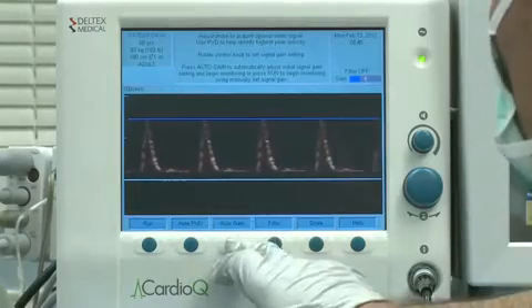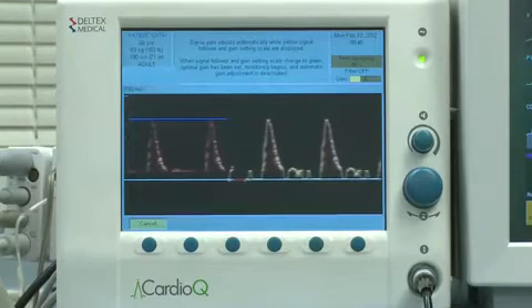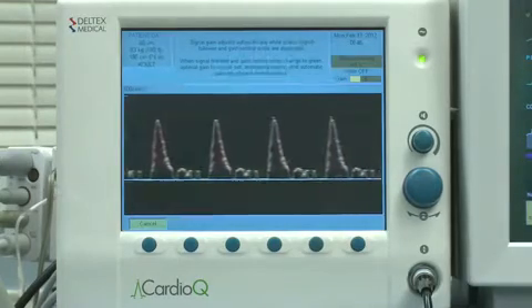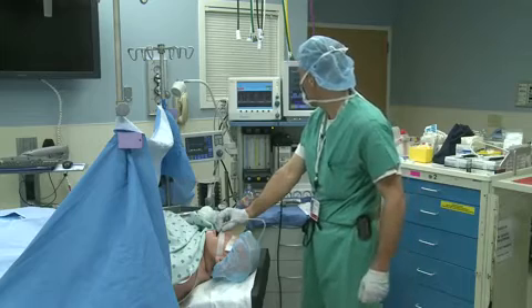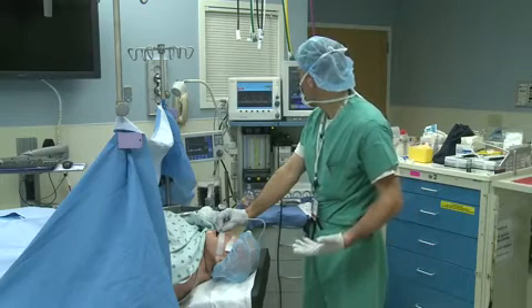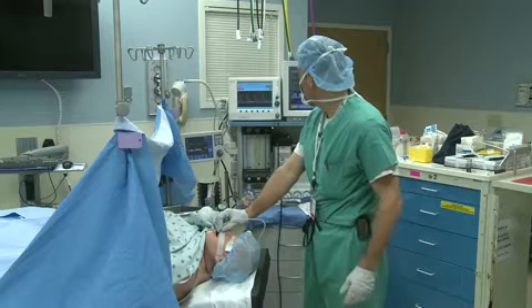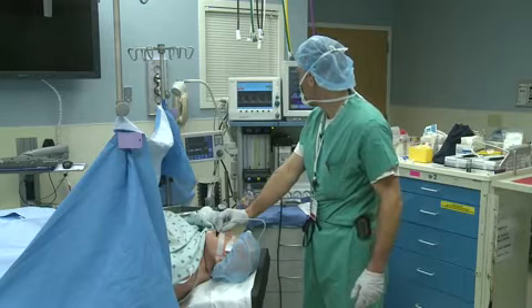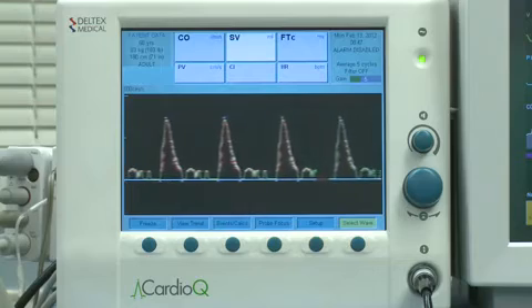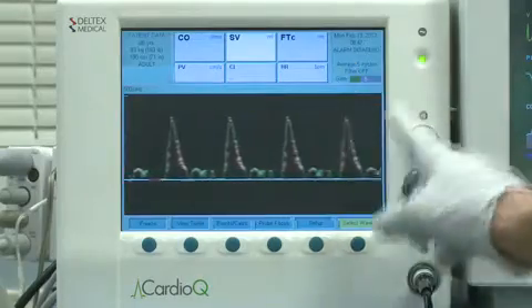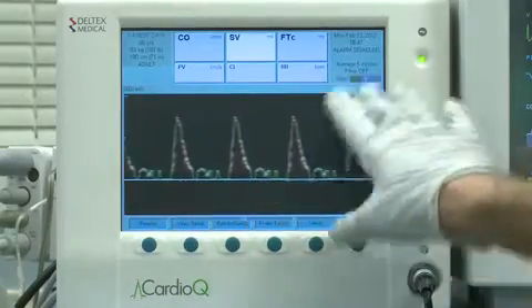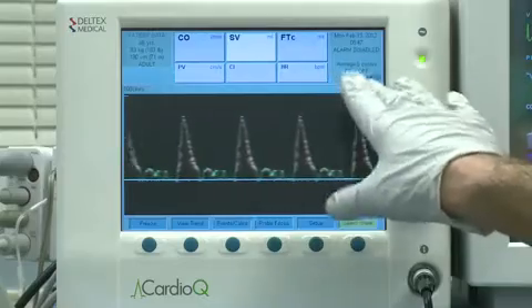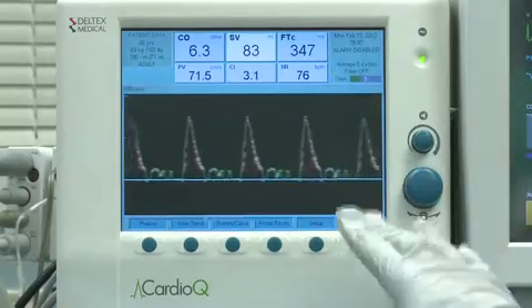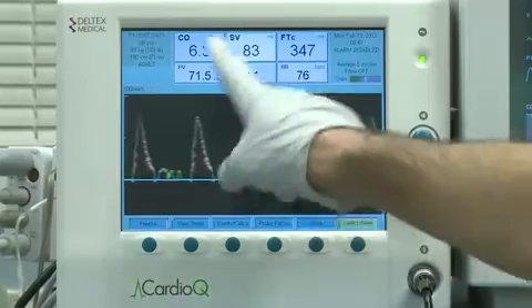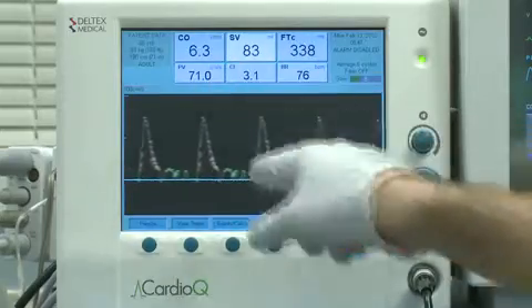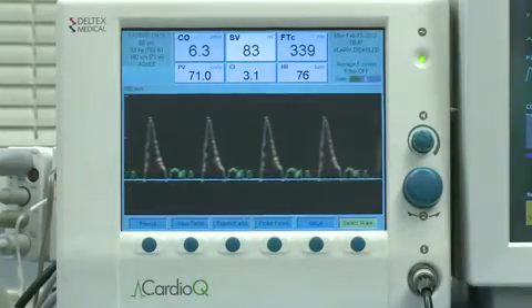And then you can hit the auto gain button, which will optimize the signal-to-noise ratio of the probe. And that takes a few seconds to go through the algorithm to figure out what the best signal-to-noise ratio is. And it found the gain was around 5, so it was right in the middle. And then, depending on how many cycles you have set, you'll start to obtain numbers for cardiac output, stroke volume, whatever parameters you have set in the cardio-Q monitor.